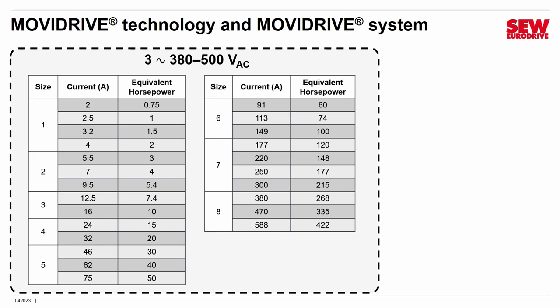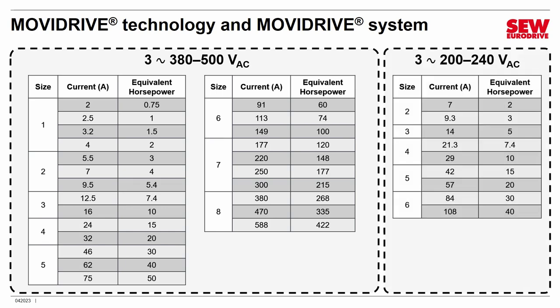That's quite a gamut of motor sizes, from little motors to pretty big ones. We also sell a lower-voltage three-phase version at 200 to 240 volts — typically 230 to 240 in the United States. That version only goes up to sizes 2 through 6, with current ratings from 7 amperes to 108, or about 2 to 40 horsepower. But if you have that lower three-phase voltage, it is available.